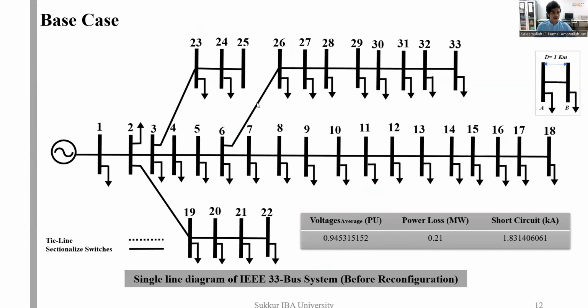So this is the base case of IEEE 33 bus system, where the distance between two buses is 1 kilometer, and the tie line is presented by a dotted line, where sectionalized switches are presented as shown. So this is the single line diagram of IEEE 33 bus system, whose average voltage in per unit is 0.945. Power loss is 0.21 megawatt, and short circuit current in kiloampere is 1.8314.